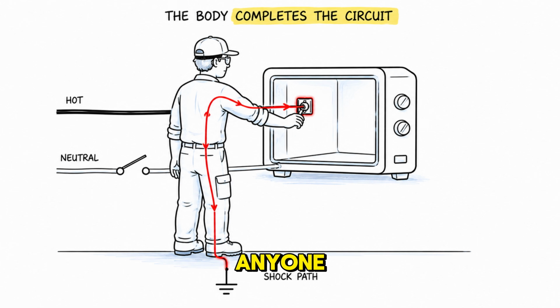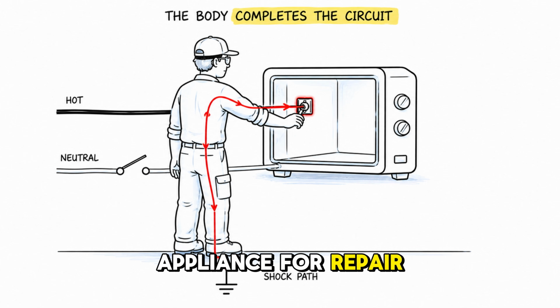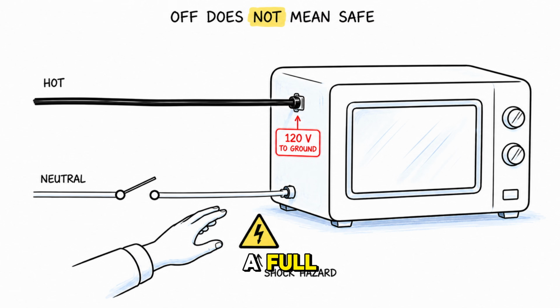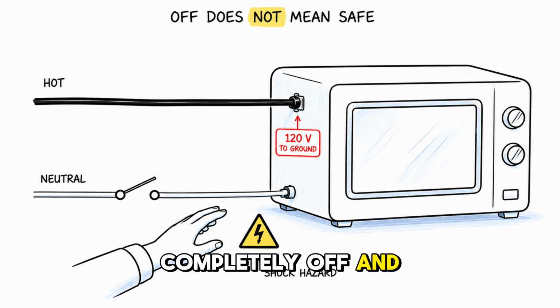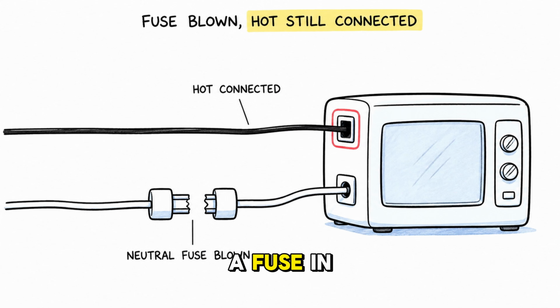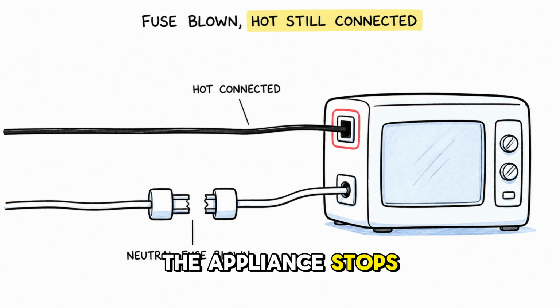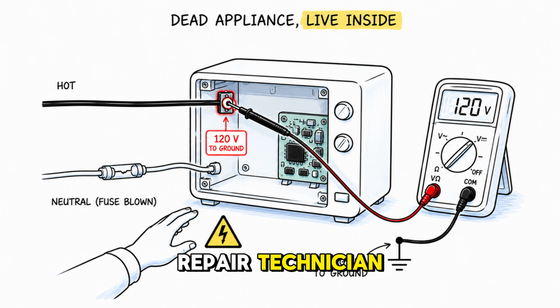In this condition, anyone who opens the appliance for repair, replaces an internal component, or touches any internal metal part will complete the circuit through their body to the ground. They will receive a full 120-volt shock, even though the appliance appeared completely off and was not running at all. A fuse in the neutral wire creates exactly the same hazard. When a neutral fuse blows, the appliance stops. The homeowner or repair technician assumes it is safe because nothing is running.